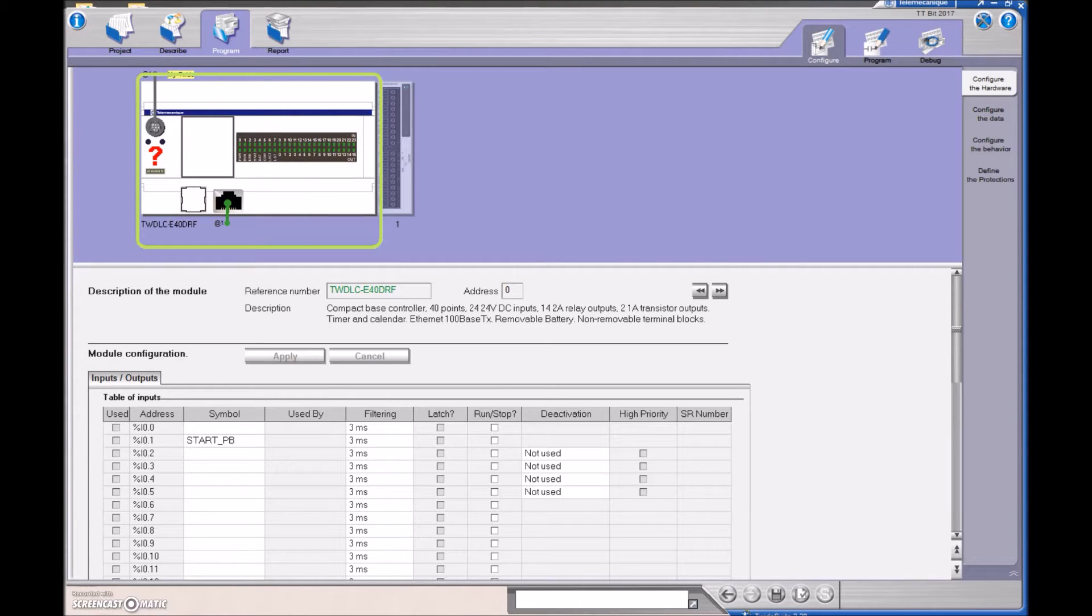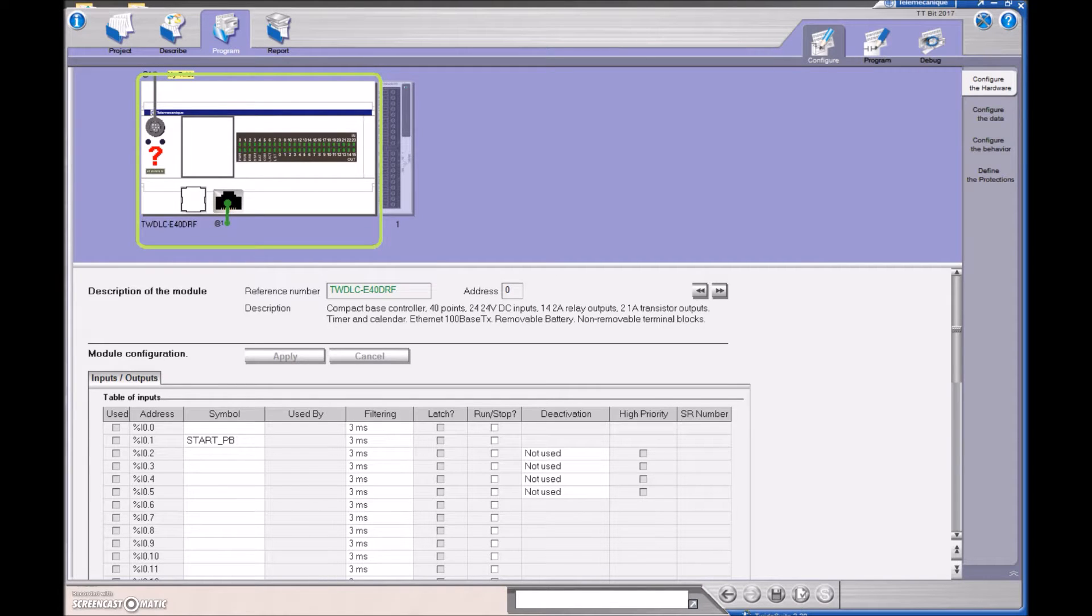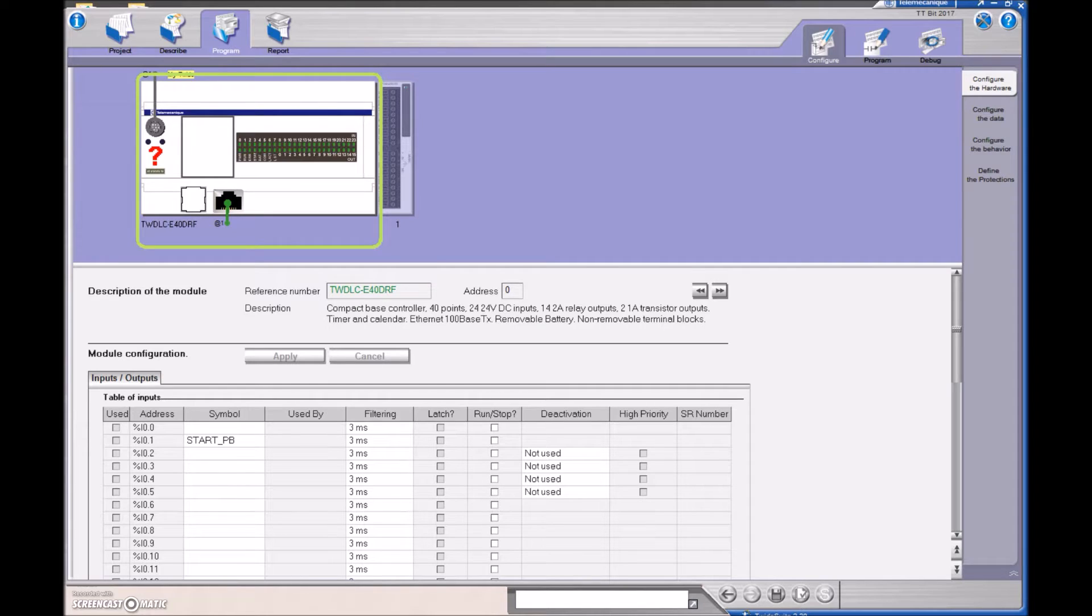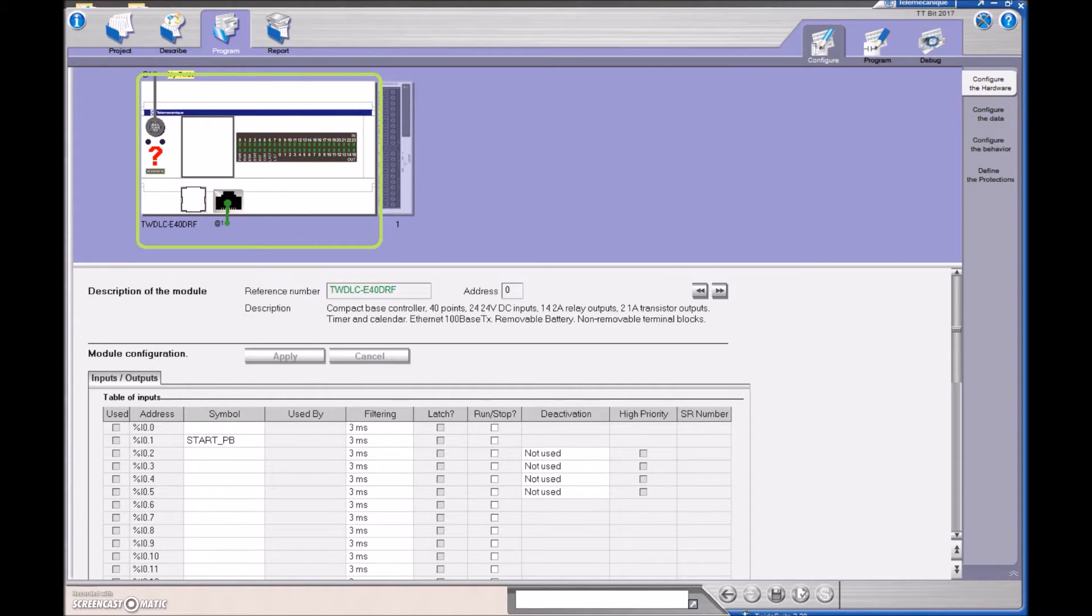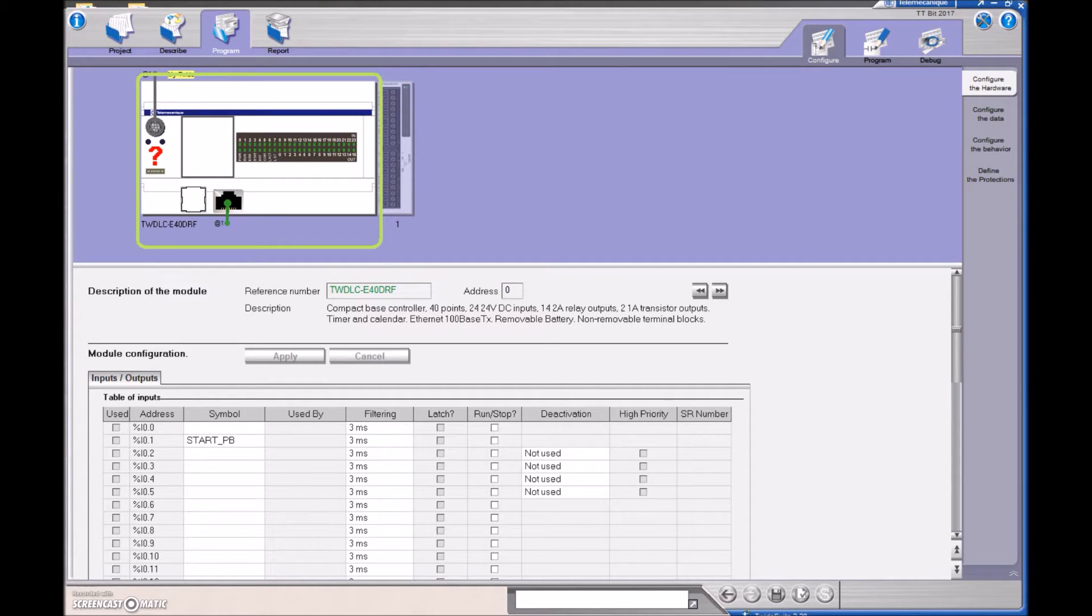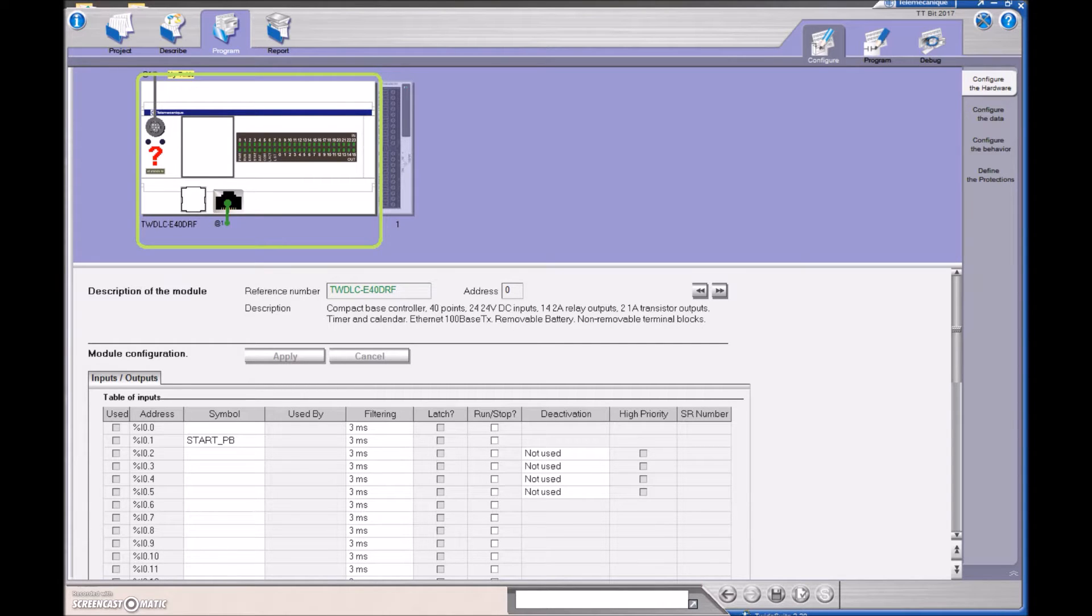Alright guys, this video is going to go over the TT bit. Now what's a TT bit? A TT bit is a timer timing bit, meaning that as the value on the timer is accumulating before it gets to the preset value, we need to have a bit that turns on. Now in the Twido Suite, they do not have a specific TT bit. They have the Q as the output bit, but they don't have a TT bit. But it's a quick and easy fix in order to create something to mimic that bit that's available on the Allen-Bradley PLCs.